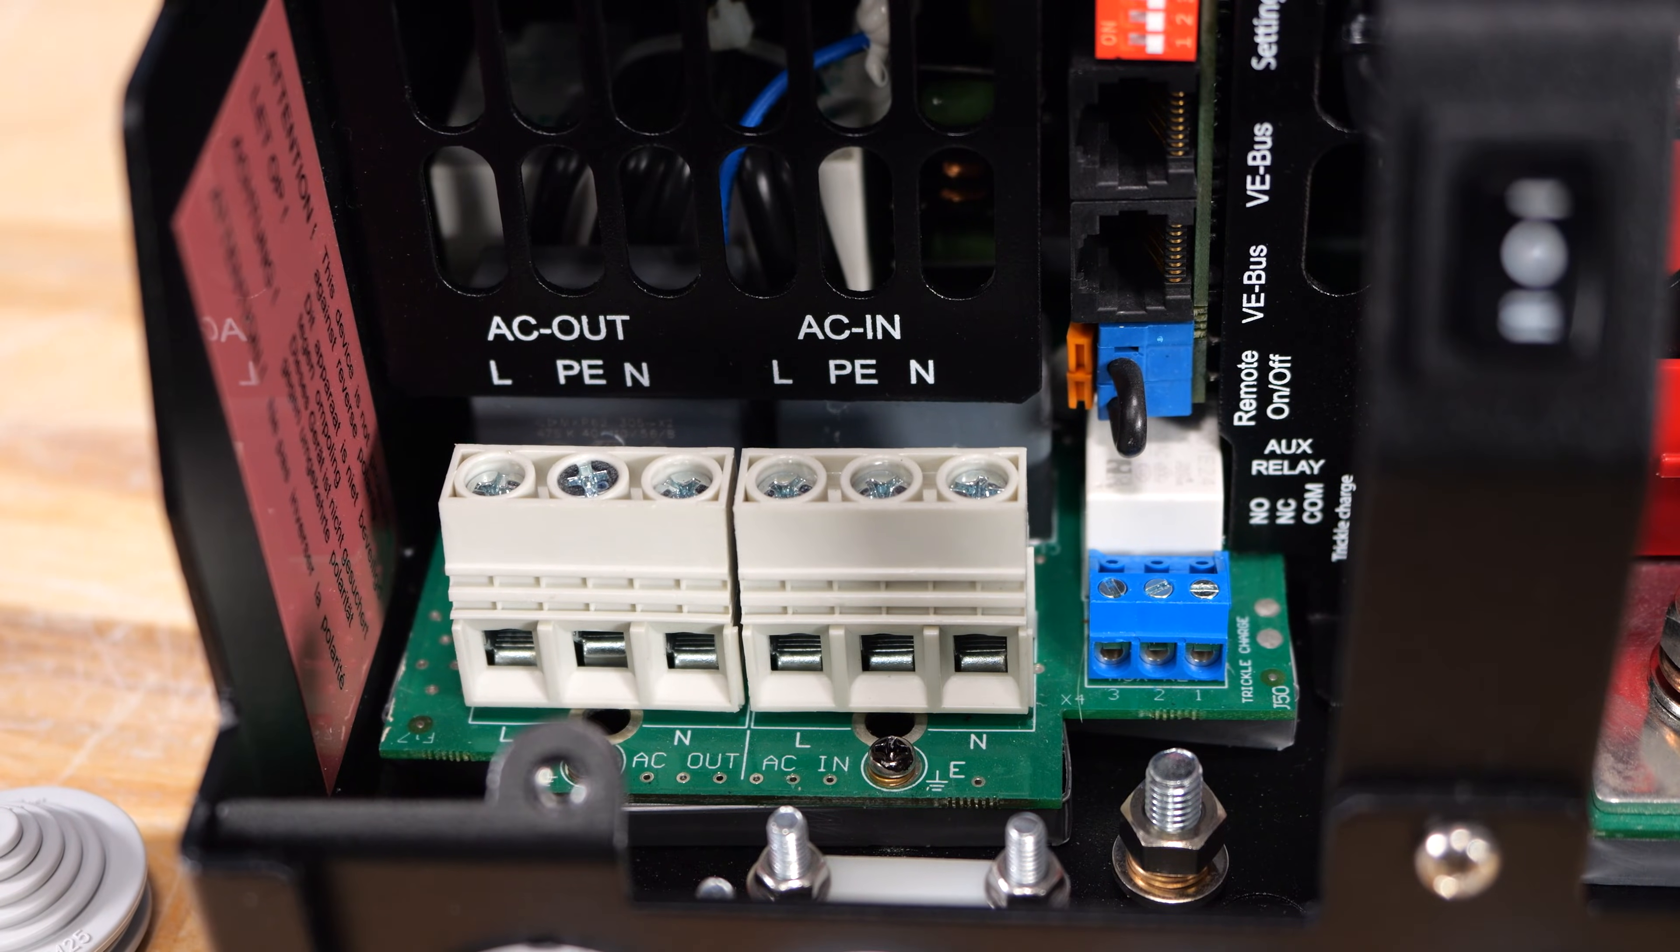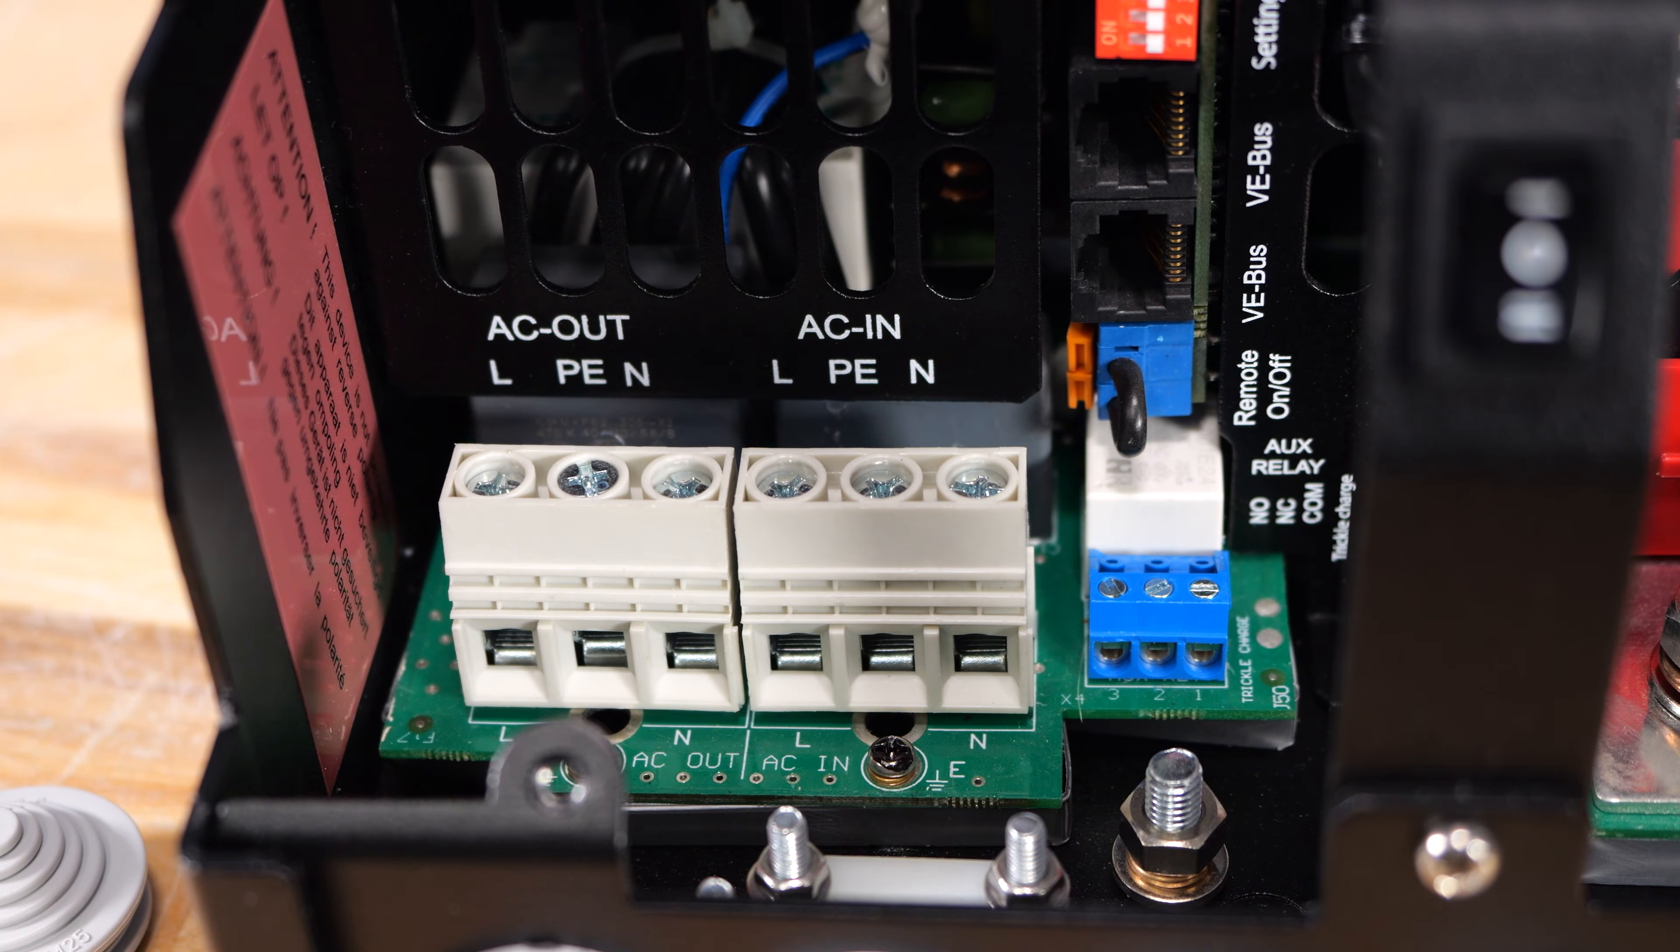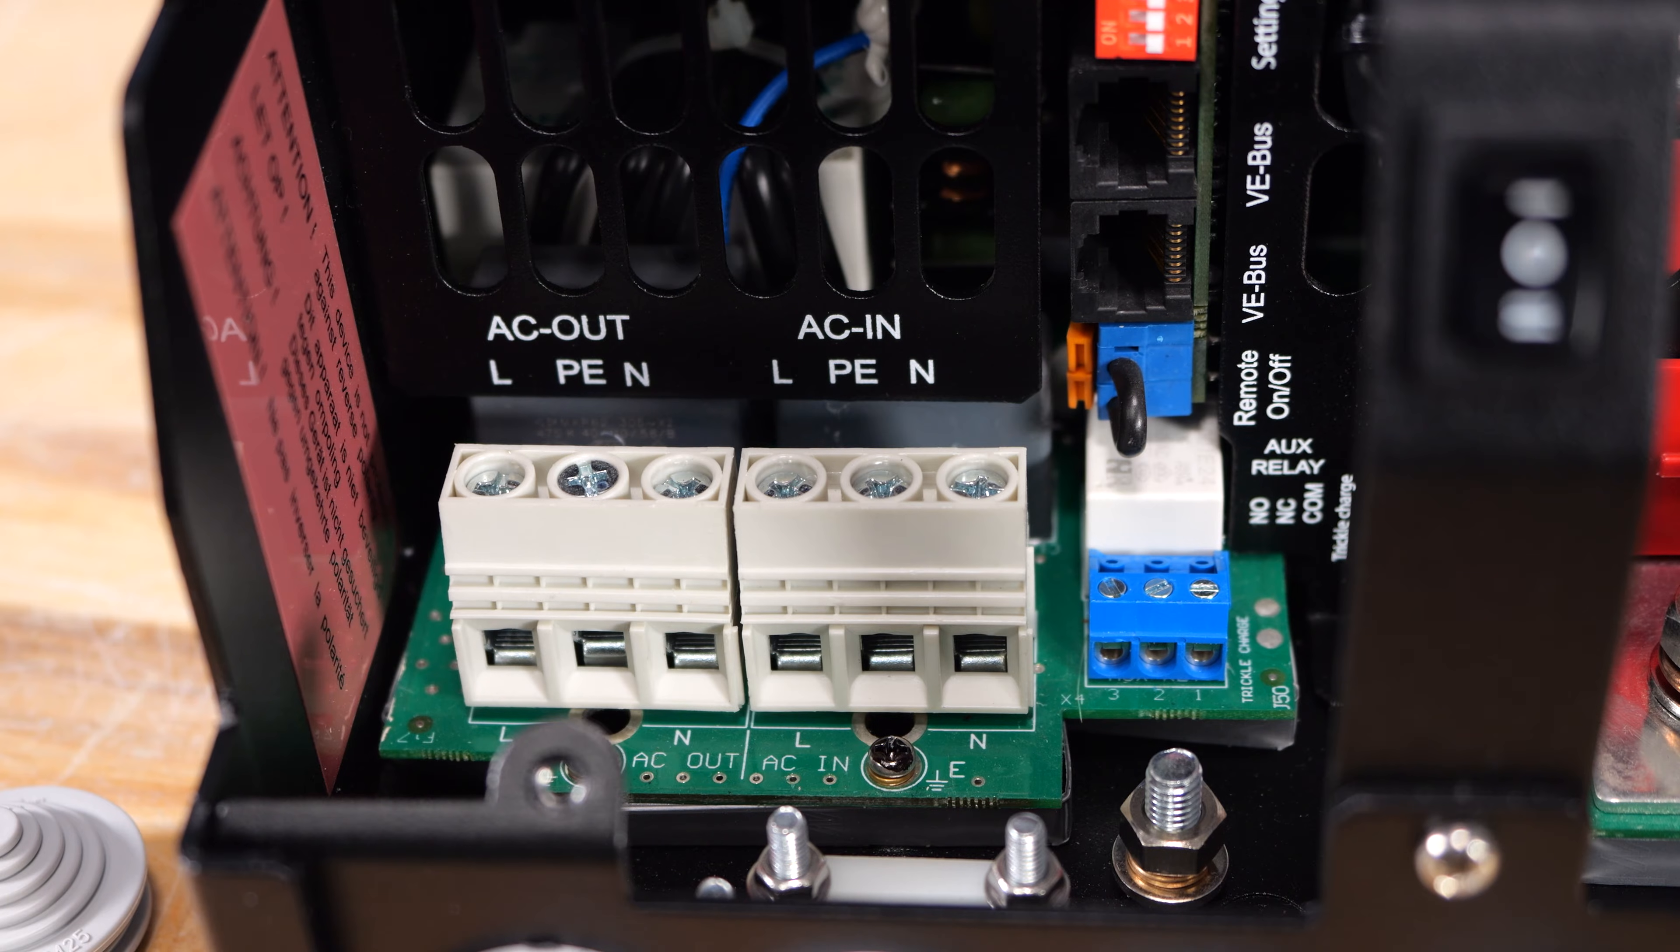Looking back at Victron's previous versions of this inverter, it is very much like the MultiPlus Compact where there is no secondary AC output. Typically Victron MultiPlus 2 inverters have a second AC output port where you have that output on when input is available. That second AC output is typically useful when you're running non-critical loads that you only want on when supplemental AC input power is available. Now that said, you still could use one of these auxiliary output relays to turn on a contactor for those type of loads.